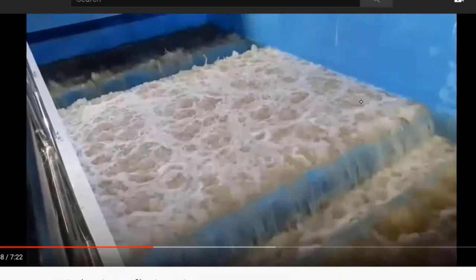Okay, so now what they've done is they've started to pump water. And notice here, you can see what's happened is they've fluidized that bed to dislodge particles. You want the media to remain below the top of the gullets, but you can see how violent this mixing is. And water is now flowing over the top of these troughs. And that's this dirty water that contains all of the removed particles.